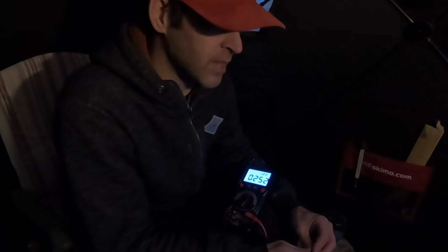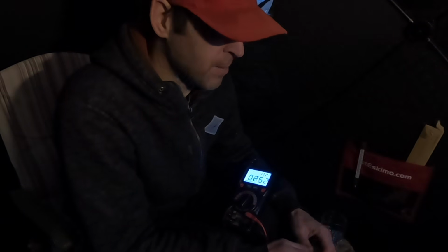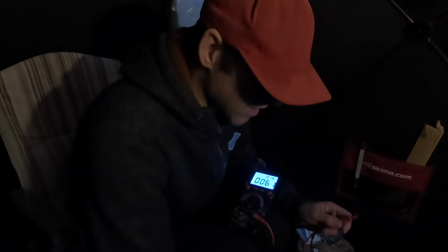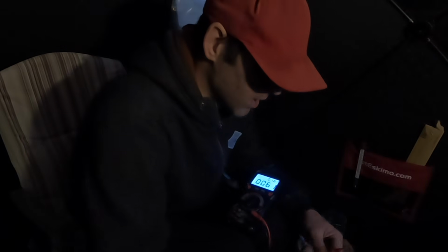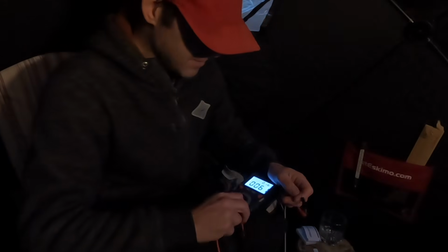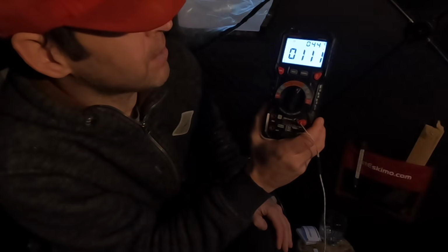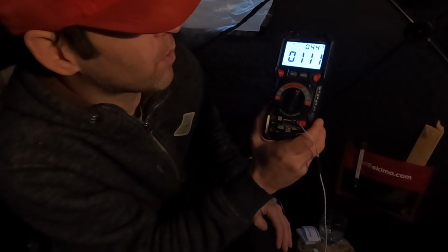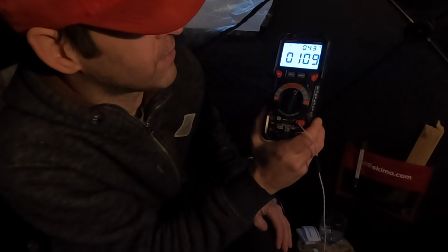Let's check the outlet temperature now and see if it's gone up. The last time we checked, it was 38 Celsius, about 100 Fahrenheit. Now the outlet temperature is up to 44 Celsius, 111 Fahrenheit.